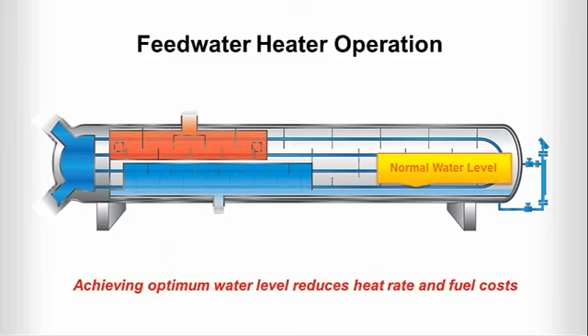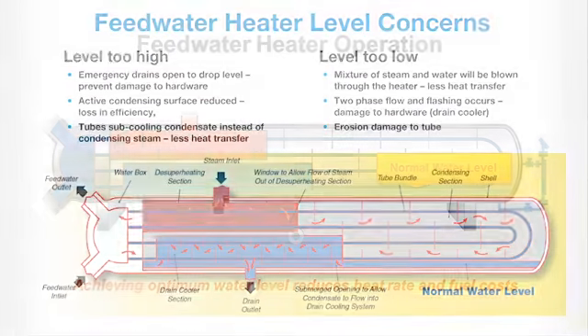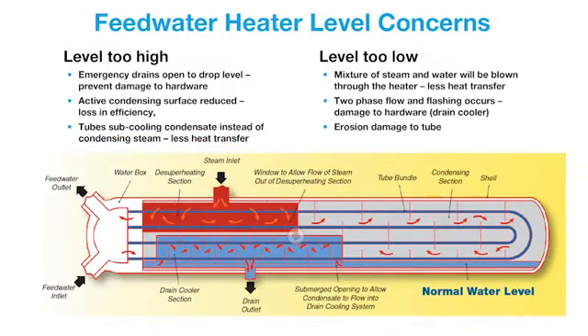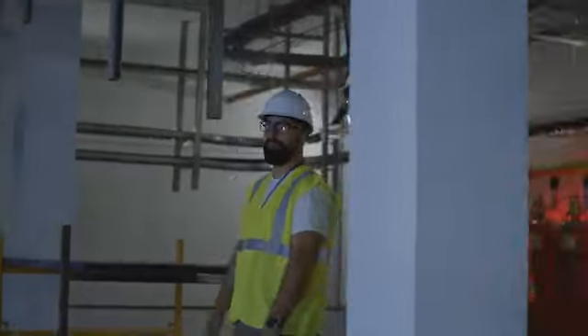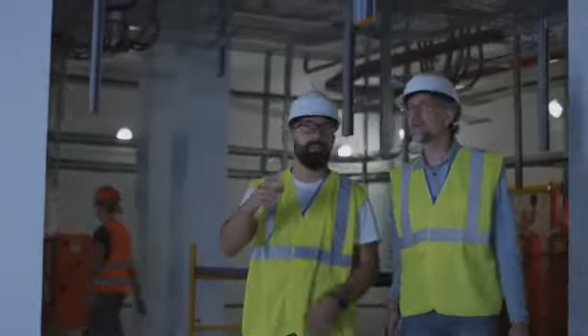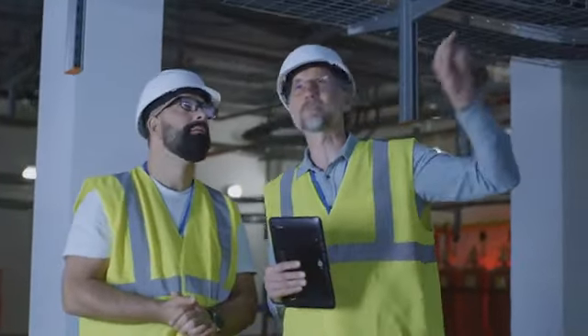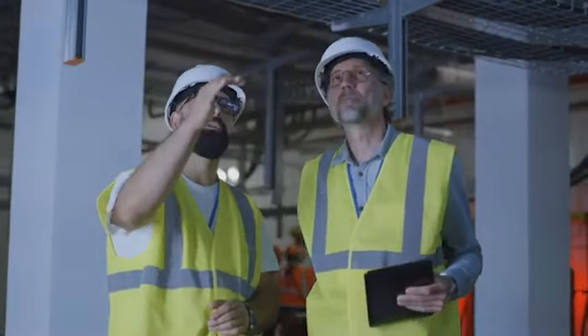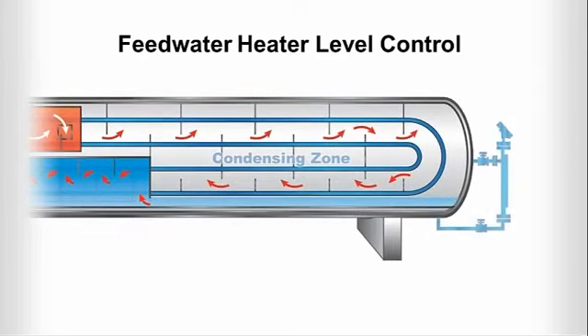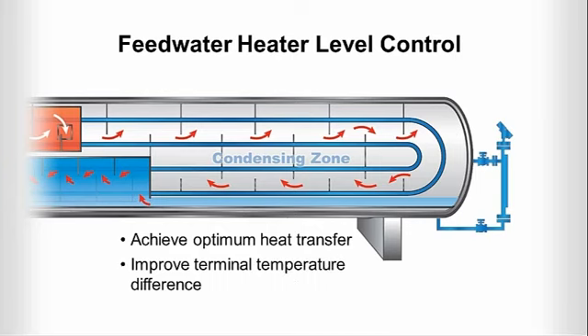Achieving optimum water level in a feed water heater is a critical component of maximizing energy transfer and minimizing controllable losses. Precision control of the feed water heater during base load and cycling operations provides operators with the high degree of data certainty necessary to optimize the feed water heater condensing zone. This is important for improved heat transfer during the condensation process. This will have a profound impact on the final feed water heater temperature and ultimately heat rate, all without jeopardizing expensive hardware. There are normally 6 to 7 stages of feed water heating. Making an investment in level control can help you achieve optimum heat transfer and improve terminal temperature difference to provide a significant return on investment.